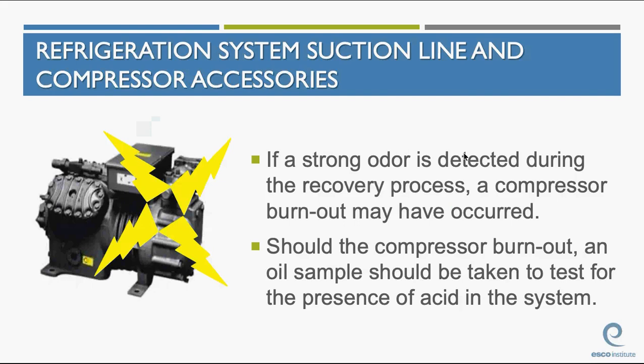If a strong odor is detected during the recovery process, in other words, if you smell a nasty combination of rotten egg and burning electrical smell out of the oil, or if you have some severe foam, that's not a white-colored foam, it's an off-colored foaming in the oil, there's a compressor burnout that either has occurred or is starting. You've got to take an oil sample to test for the presence of acid in the system. Because if you put in a new compressor and there's acid in the system, you're going to right away burn out that system again.